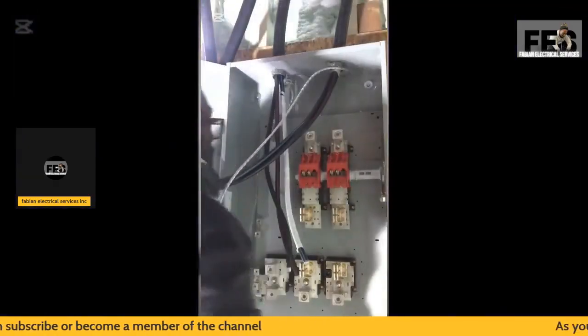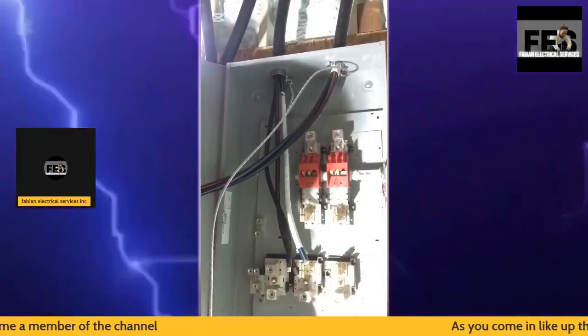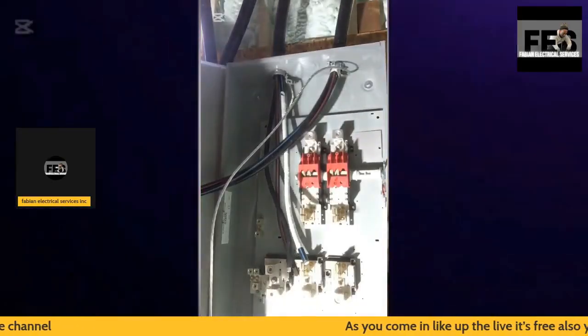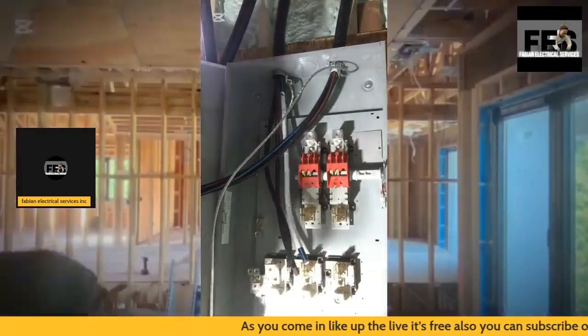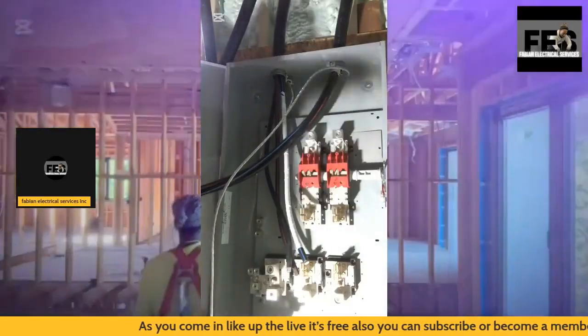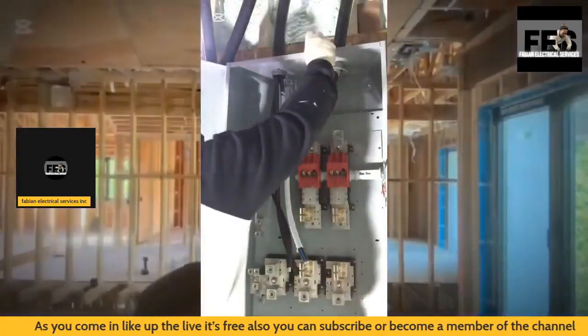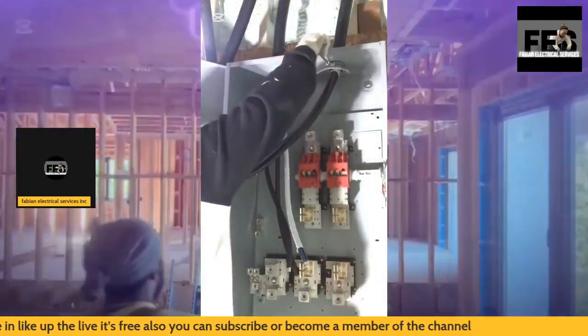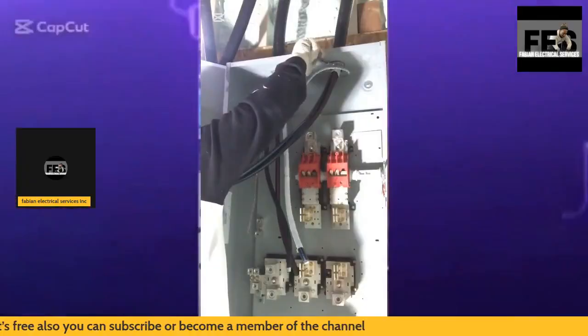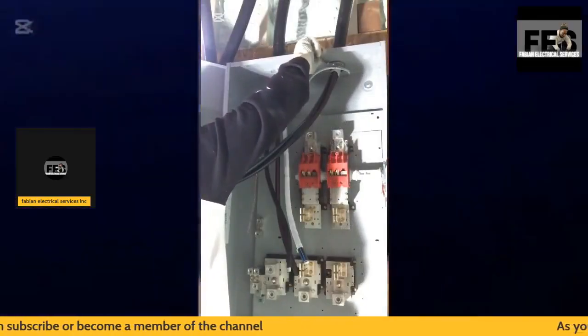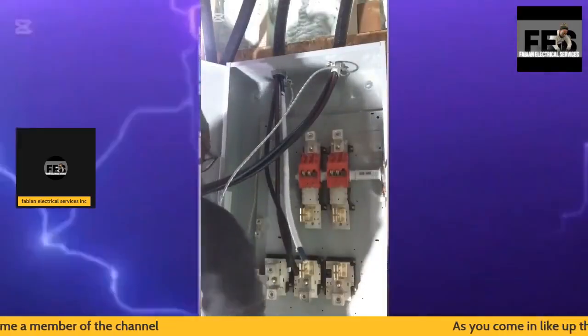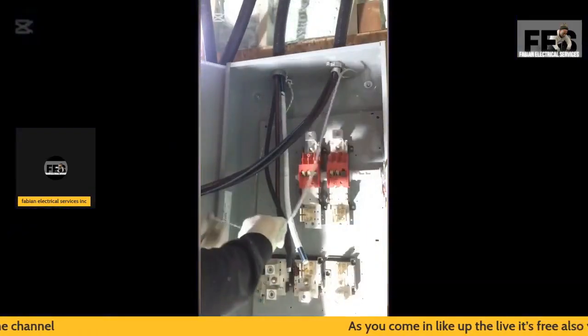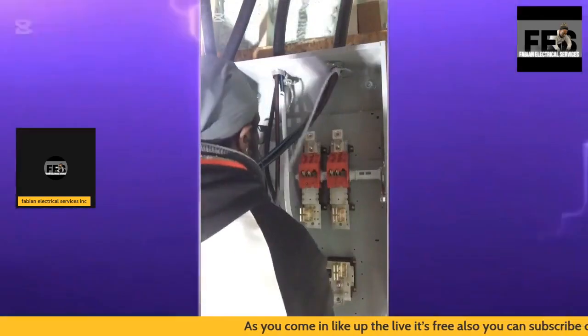As you can see, the reason I like to keep the white paper on is that it simply helps with the cable. The cable is locked in place. Once you disassemble that, it gives you a lot more problems getting the cable inside of the connector. So I always make sure I land my cables inside of the connectors in the disconnect, and then I make sure I remove that.